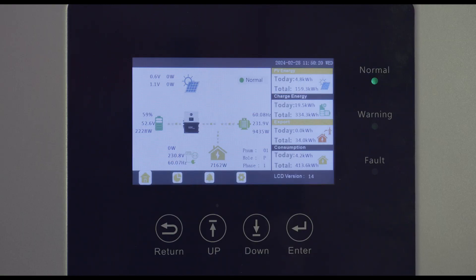You can see on the 18k PV screen that when I change the rated generator output from 10kW to 5kW, the inverter will start discharging to pick up the 3kW slack on our 8kW load.